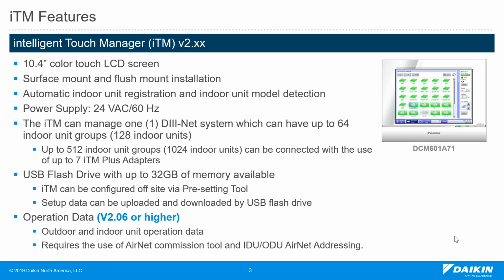As most of you already know, the ITM is a color touch screen, 10-inch screen. It could be surface mount or flush mount. I think most of you are already aware of this. We can do automatic indoor unit registration and indoor unit model detection. This function is supported by the ITM. Not all competitors have the same easy commissioning method, but it will be highlighted in the next slide. Power supply requires a 24-volt power supply.